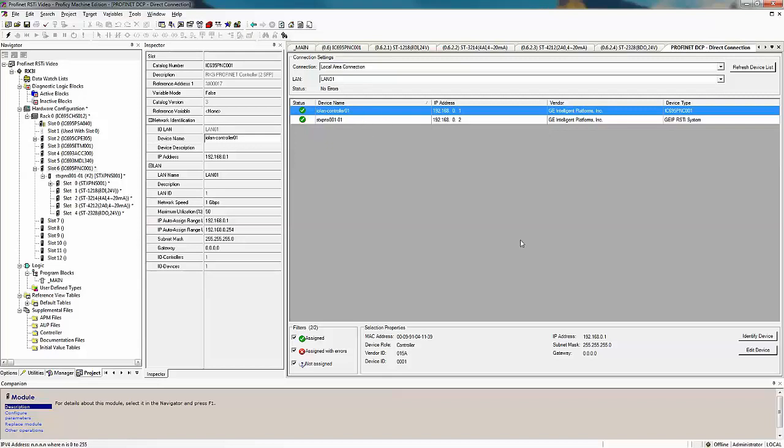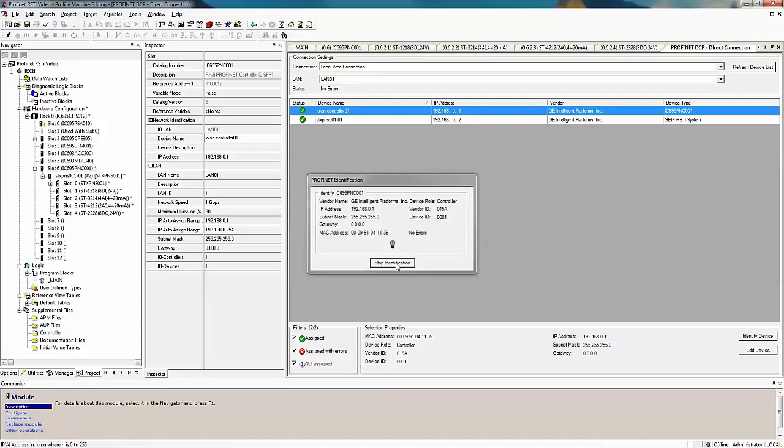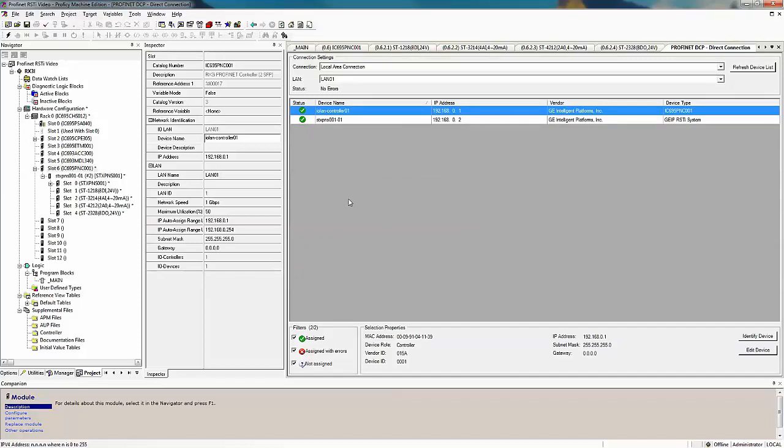If I want to identify my devices I can highlight a device and hit identify. When I click on the identify it will make the lights on my PROFINET controller flash in kind of a ring pattern so you can see which device you're looking at. If you have multiple devices you can highlight them here, hit identify device, and then be able to see which device is actually out in your system. The important thing to remember is that your PROFINET controller must be connected to the local area LAN for this part of the configuration. Once you get it all set up you can disconnect it and have it just be on its own, but for this discovery tool to work they need to be tied together for the initial configuration.